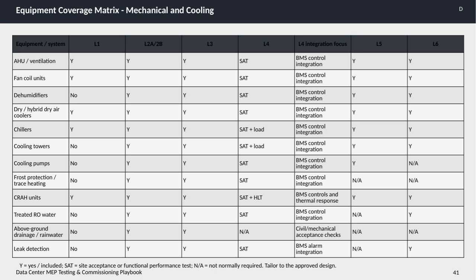The matrix also shows specific focus areas at L4 integration, such as BMS control integration, thermal response for CRAH units, and civil or mechanical acceptance checks for drainage systems. Finally, the legend clarifies a notation. Y means the equipment is included in that level of testing. SAT refers to site acceptance or functional performance tests, and not applicable indicates that a test is not normally required and should be tailored to the approved design. Overall, this matrix helps ensure that all mechanical and cooling equipment undergoes the appropriate level of scrutiny to maintain operational reliability in the data center environment.